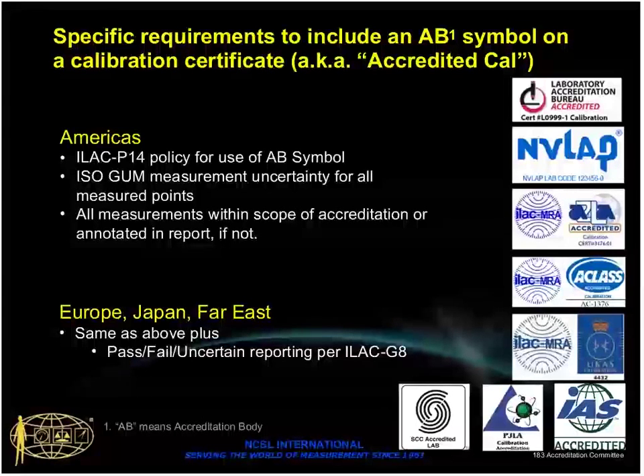Likewise, with the uncertainties of measurement, there are various schools of thought about how to calculate uncertainty of measurement. I think over the years it's getting more unified, and people are using the GUM, the Guide to Uncertainty of Measurement from ISO, properly called Guide 98, but that itself can be further interpreted, and there are some very useful documents available. I would recommend the UKAS one, but in fact it is of worldwide repute, and we have people downloading from our website a couple of thousand a month of the document M3003, and you'll find that on the UKAS website. It's a down-to-earth interpretation of the GUM with lots of examples. There's also an EA document which is similarly useful to interpret it. So accreditation bodies facilitate the implementation of this rather heavy GUM document by having their own guidance document.